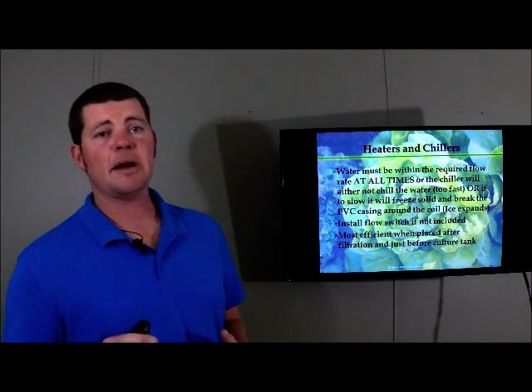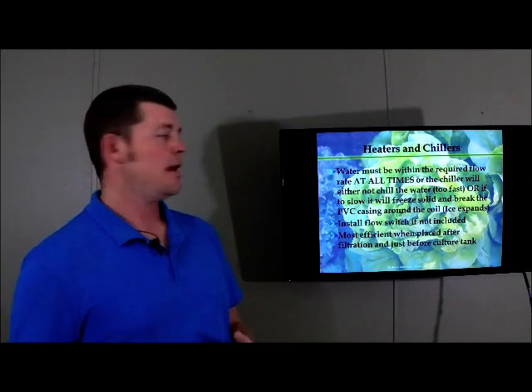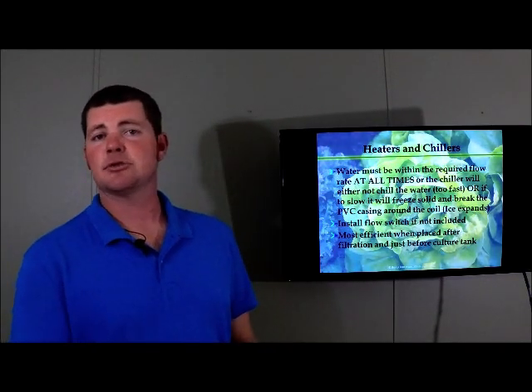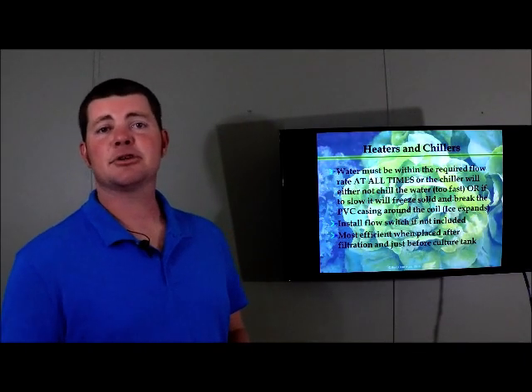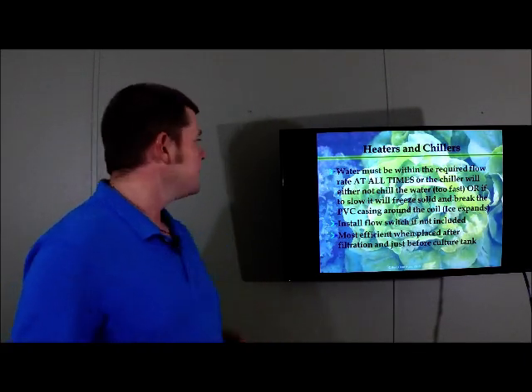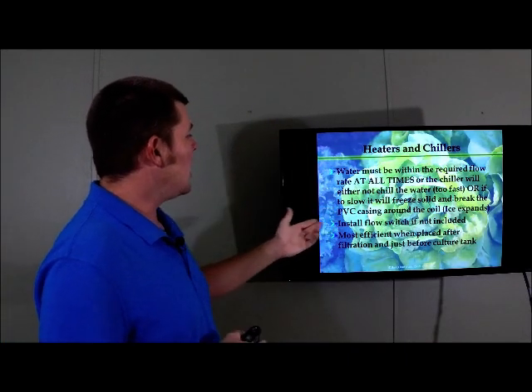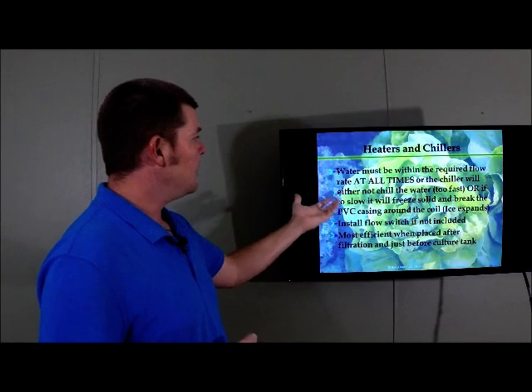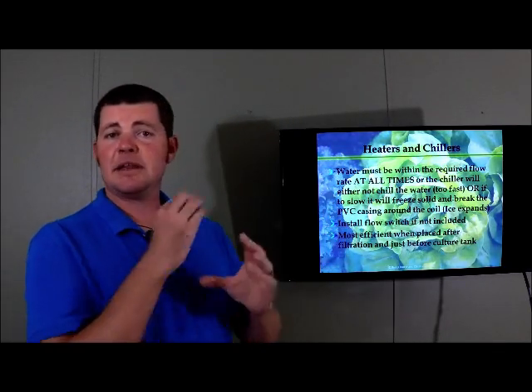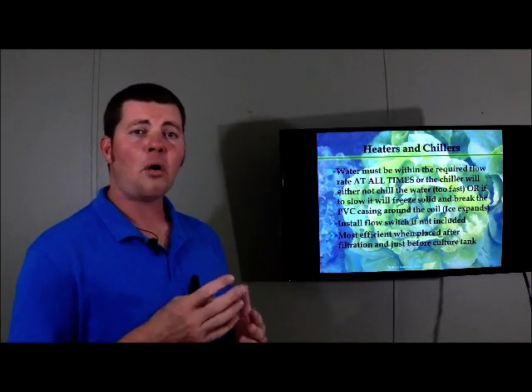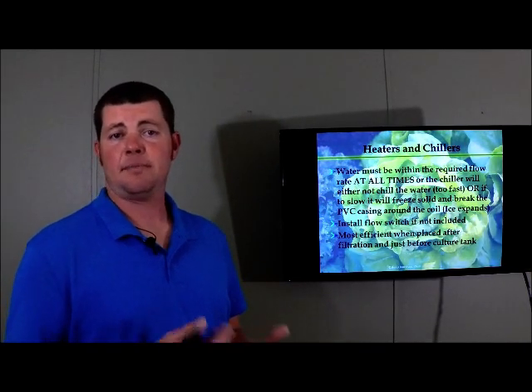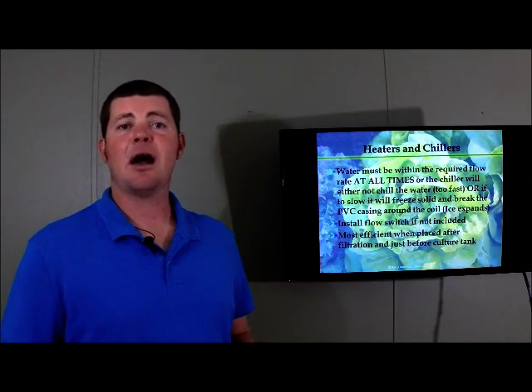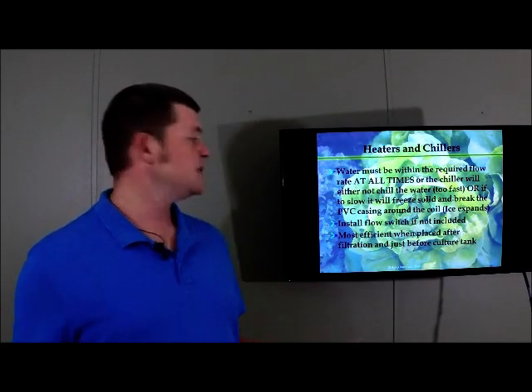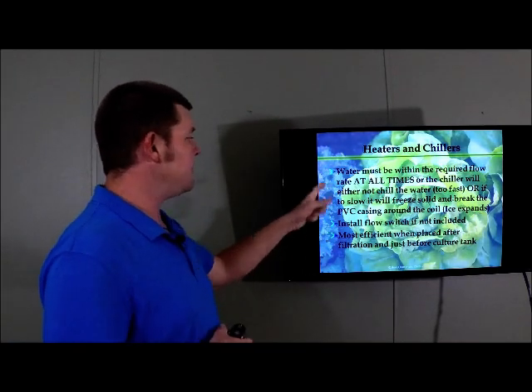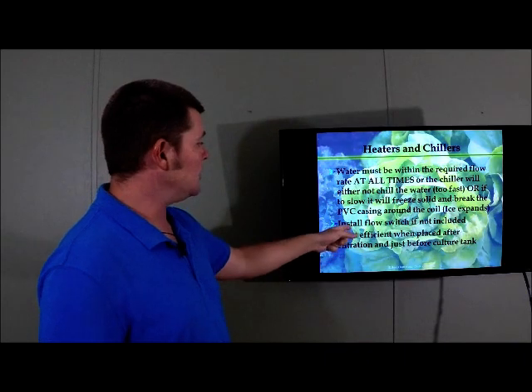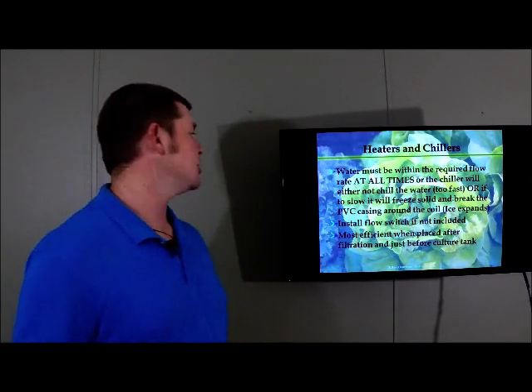So you can repair it, because you can get in there with some epoxy tape, and I've done that, to some trashed units that I was trying to bring back to life. But a manufacturer is going to say, guess what? You messed up, buy a new one. So this is very important. Some of the better chillers actually come with a flow switch that is pre-installed in that unit. So if you fall outside of the desired flow rate that's required to operate, it'll shut the chiller off so it doesn't chill, and freeze up and break itself. So that's very good. But if that unit does not come with one, you need to buy one and install it there at the inlet of the chiller.